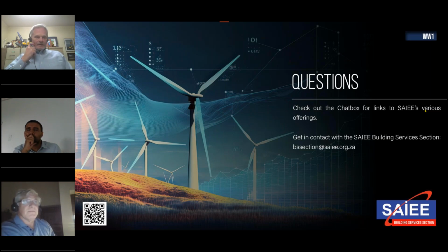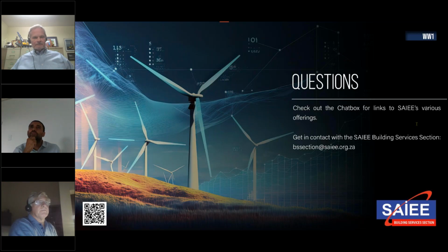Well, of course all turbines produce a wake, and a rule of thumb for spacing turbines is 8 to 10 rotor diameters downwind in the prevailing wind direction. You want to give the wind a chance to recover before you put it through a second rotor. Among wind farms, if the small turbine's rotor is below the rotor of the big turbines, that's not as much of an issue, but I think you want to follow industry rules of thumb on spacing otherwise.